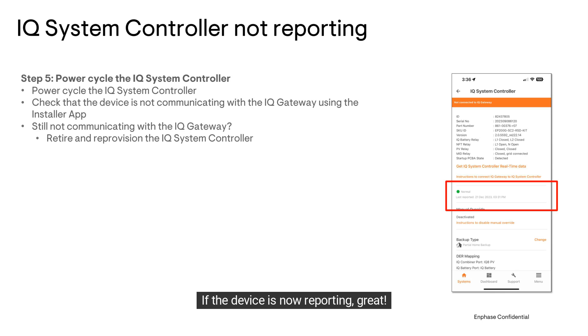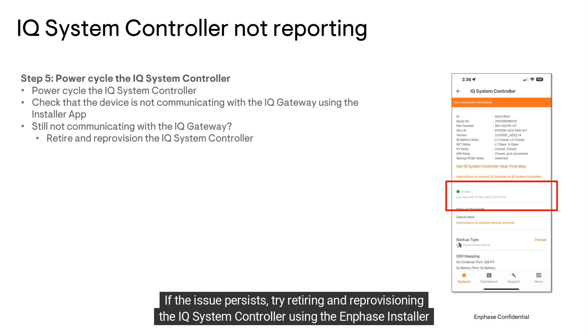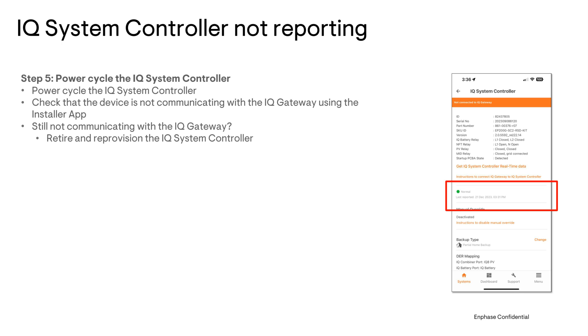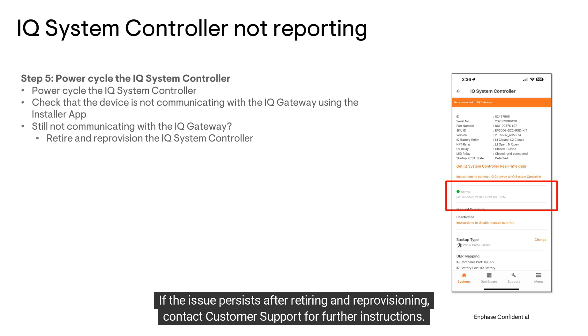If the device is now reporting, great — the issue has been resolved. If the issue persists, try retiring and re-provisioning the IQ system controller using the Enphase installer app. If the issue persists after retiring and re-provisioning, contact customer support for further instructions.